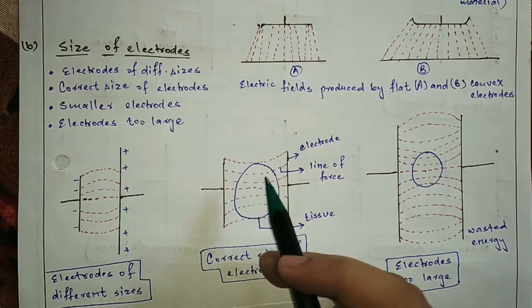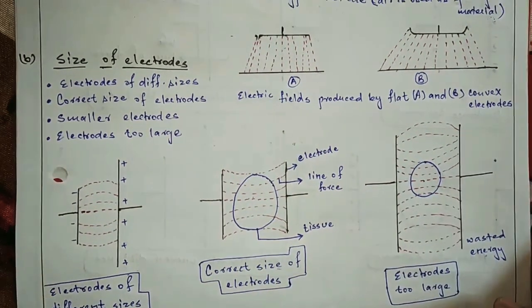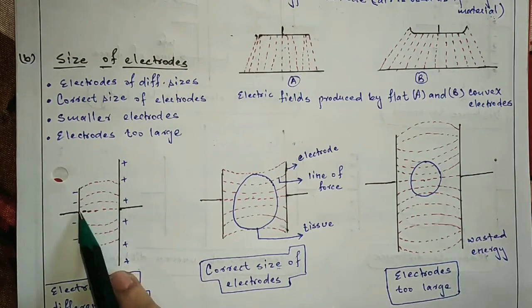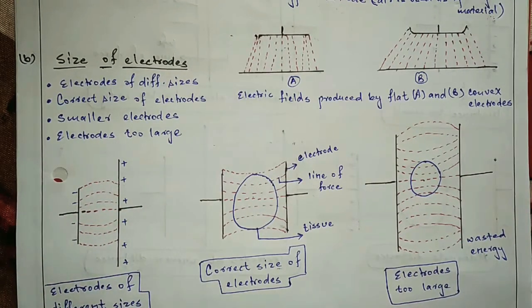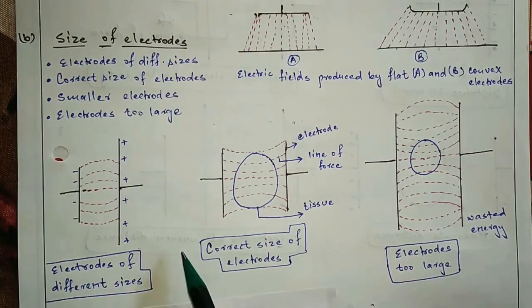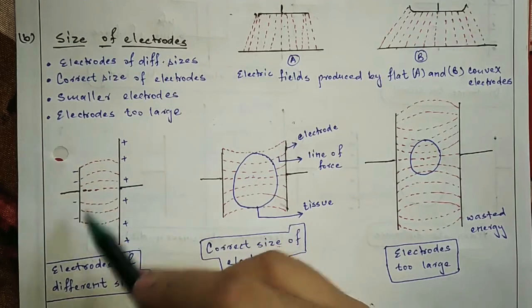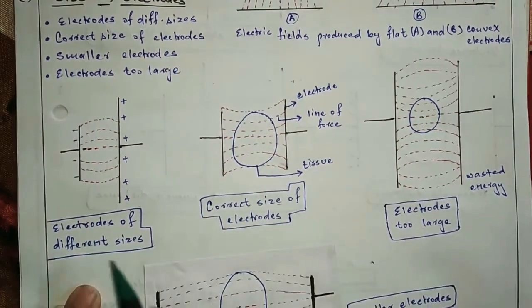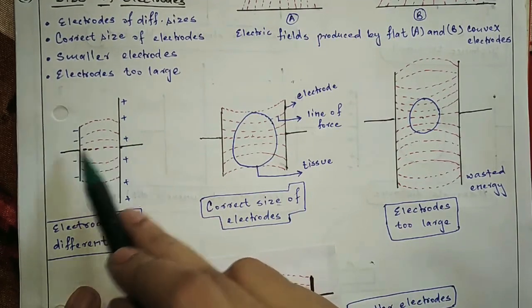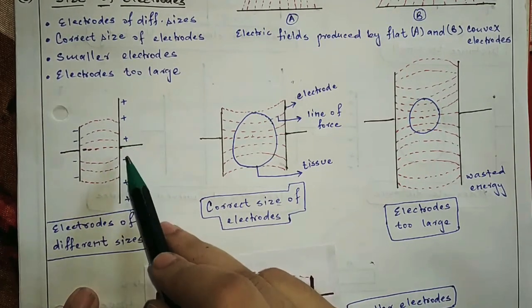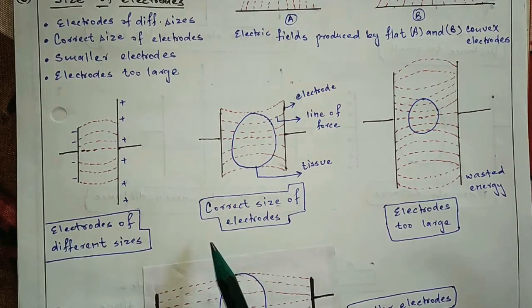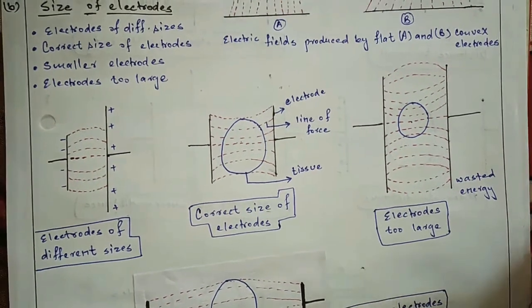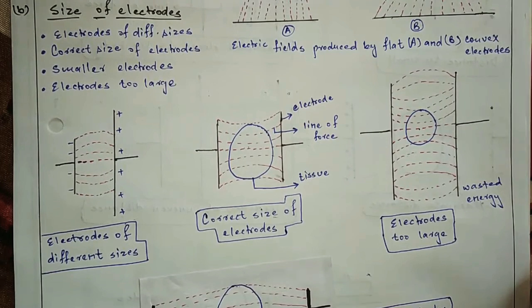Now let's talk about the size of electrode. The two electrodes should be the same size. If they are different sizes, a different magnitude of charge is required to charge them. As per the rule, the electrode should be slightly bigger than the body part to be treated.